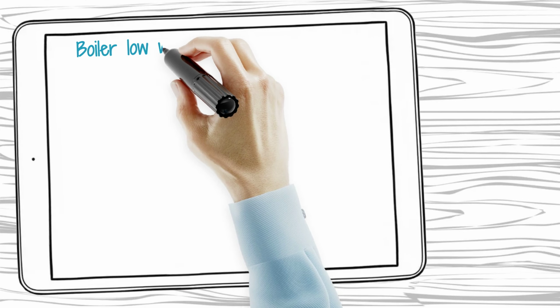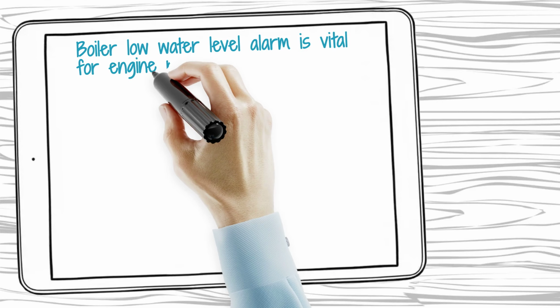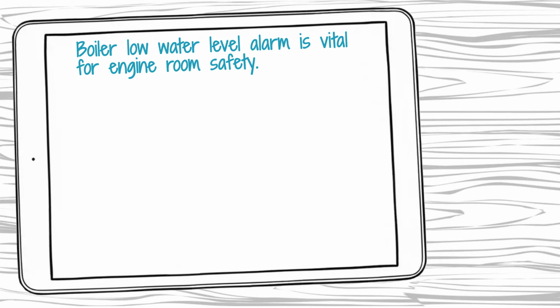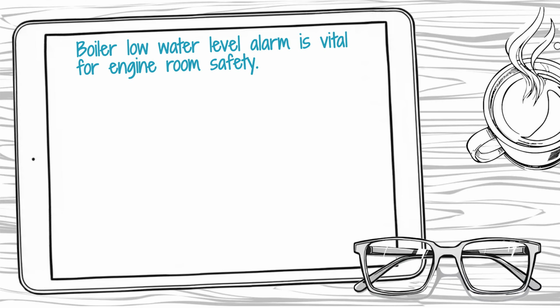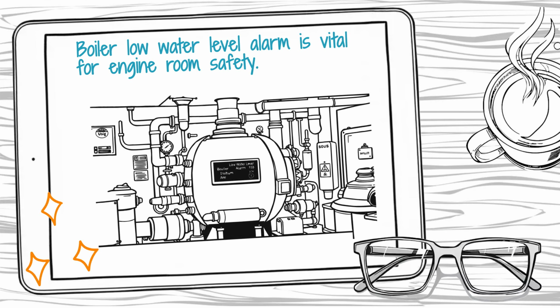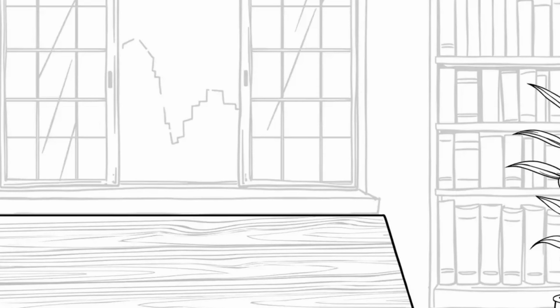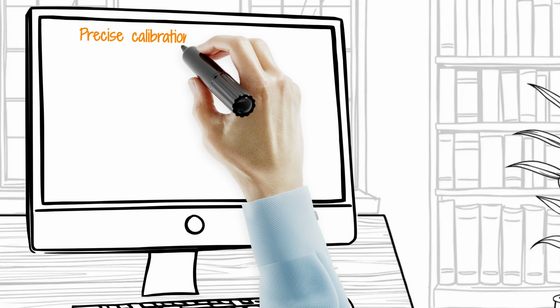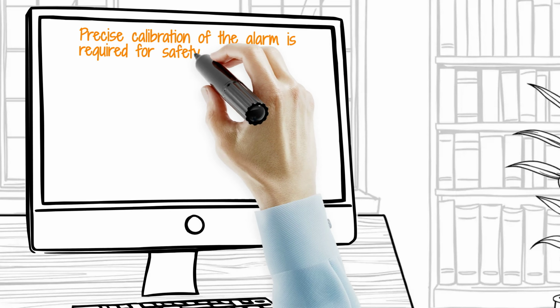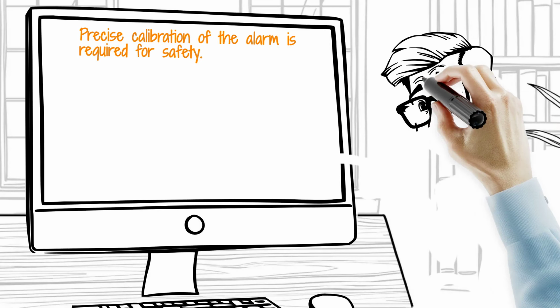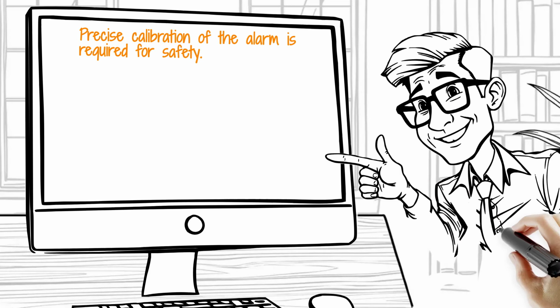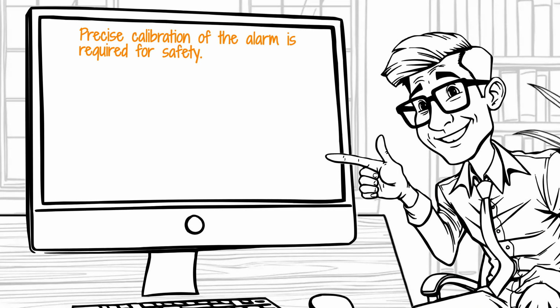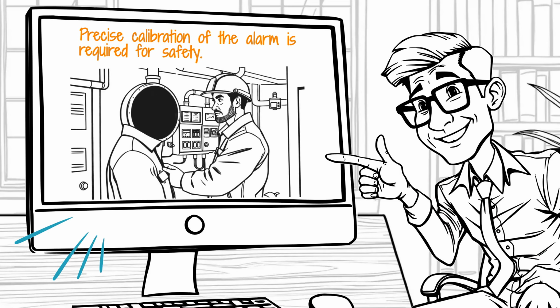In the hazardous environment of a ship engine room, the boiler low water level alarm is the most critical safety device, standing between normal operation and a catastrophic dry firing of the pressure vessel. Ensuring this alarm triggers at exactly the right moment is a non-negotiable duty for every marine engineer, requiring a precise calibration procedure that tests both the mechanical and electronic response of the system.